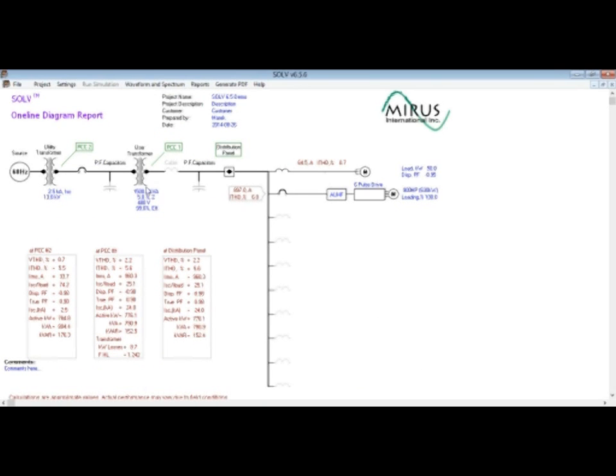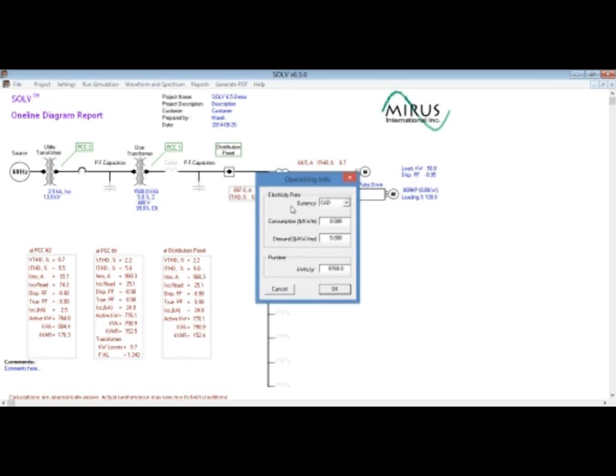We can continue our analysis by selecting different form of harmonic treatment using a second scenario option. However, before we do that, I will change the operating info for a more accurate energy analysis. So let's change the currency to American dollars, consumption to, let's say, 10 cents per kilowatt hour, and demand for $10. And let's say this particular system works 12 hours per day for 260 days a year, which is 3,120 hours in a year.